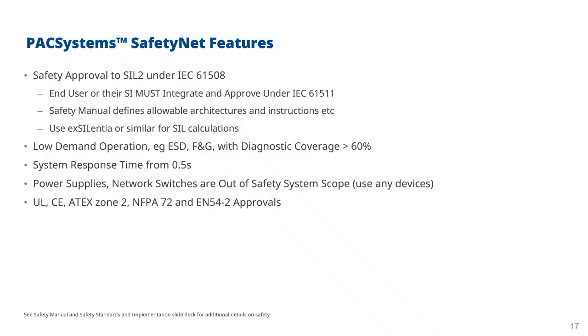But with these sorts of safety systems, normally you don't want them to operate too quickly. If they operate too quickly, you get spurious shutdowns, which can be very expensive in operational time. But also you do need to establish that there is actually an issue that needs responding to.